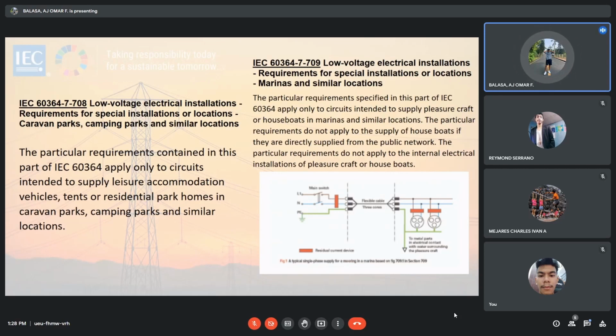This is the typical wiring in a marina. Underground cables, sheathed or non-sheathed overhead cables, mineral insulated cable with a thermoplastic covering, thermoplastic or elastomeric insulation, armored cable with extruded non-hygroscopic fibers, cables that are at least equivalent to the above. Cables suspended in free air or incorporating a support wire, or mineral insulated cables. And dito naman sa picture na ito, the cables are selected and installed so that mechanical damage due to the movement of floating structures caused by waves or tide, for example, is prevented.